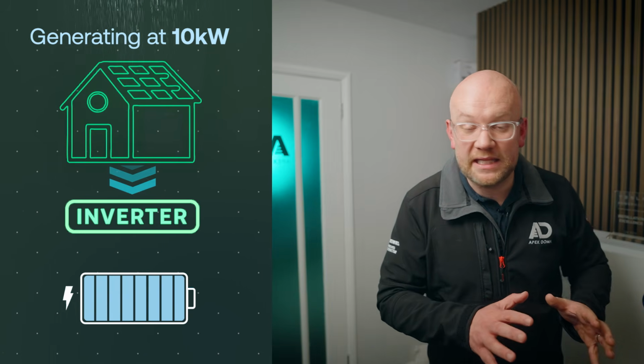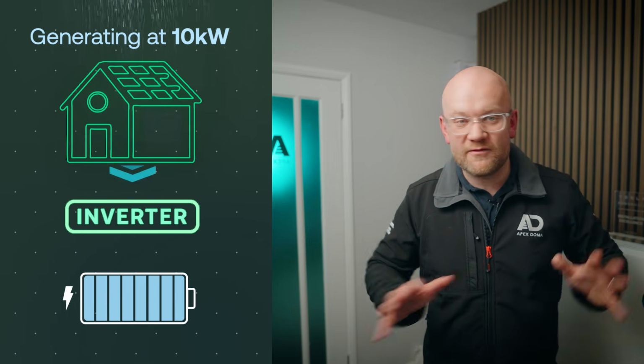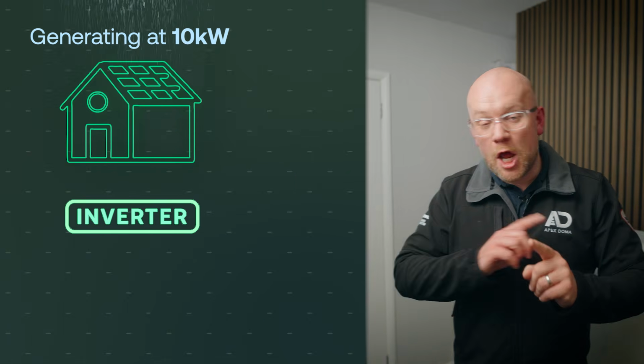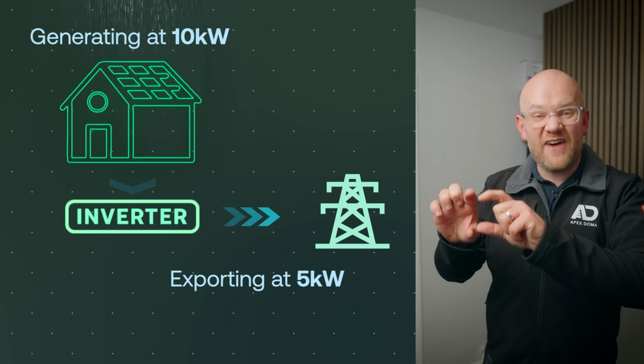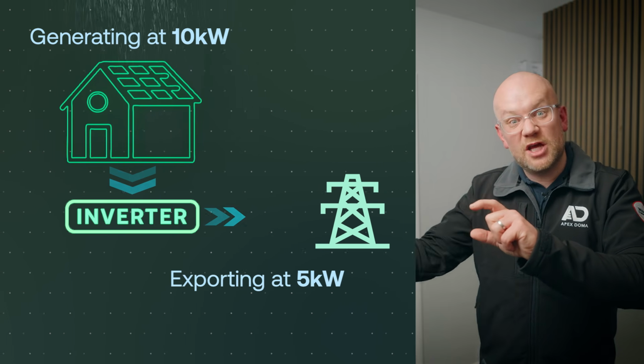But if you're restricted, this isn't restricting the amount you can send, it restricts the flow rate. So when someone says, I can only export 5 kilowatts worth of solar, what this means is if I have a 10 kilowatt solar system and 10 kilowatts is generating at full rate, which is very unlikely to happen, then effectively what happens is if your house isn't using energy, if your battery is completely full to the brim, if you're not diverting to anywhere else, then only at that point in time, your flow rate is reduced to 5 kilowatts in terms of its speed going outwards.